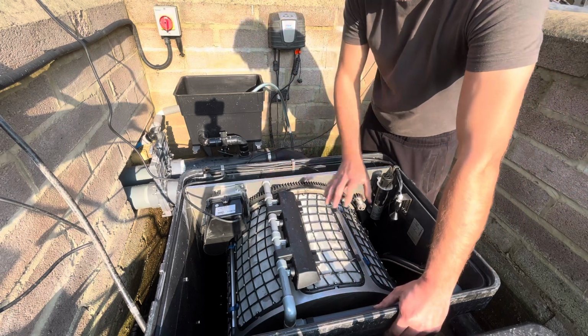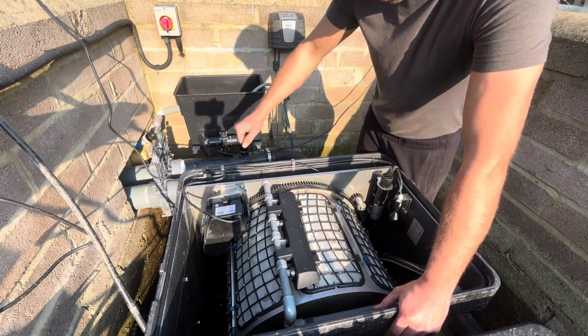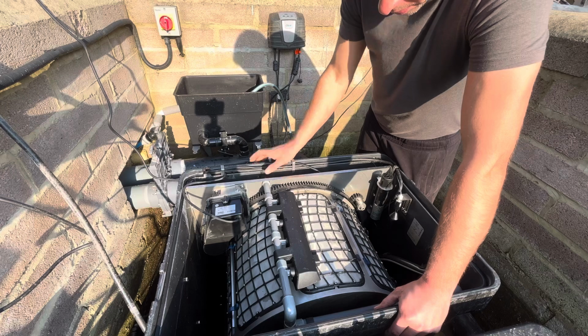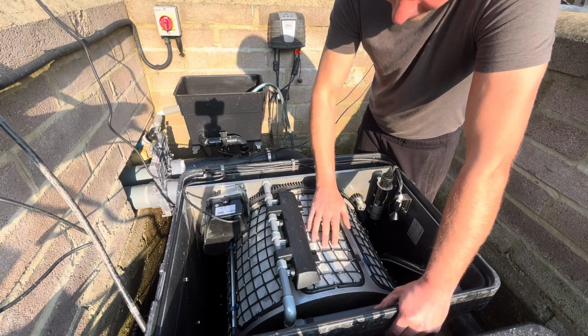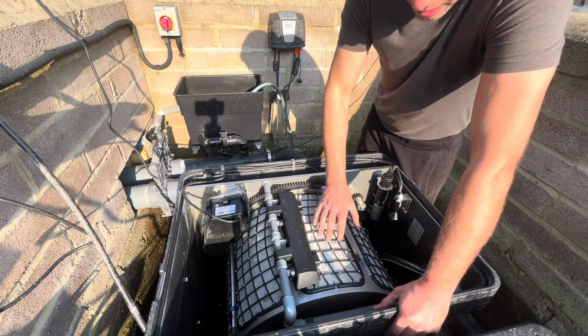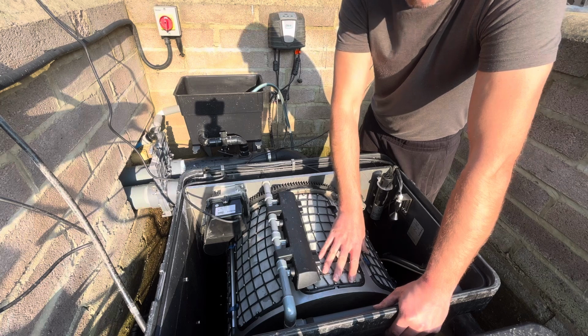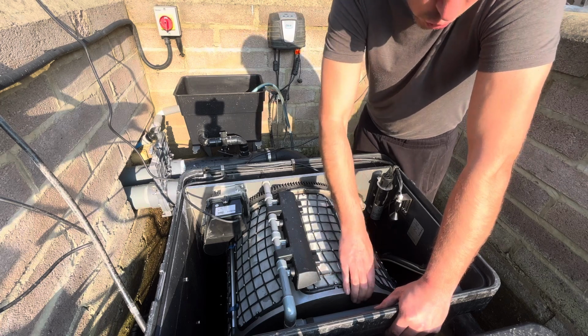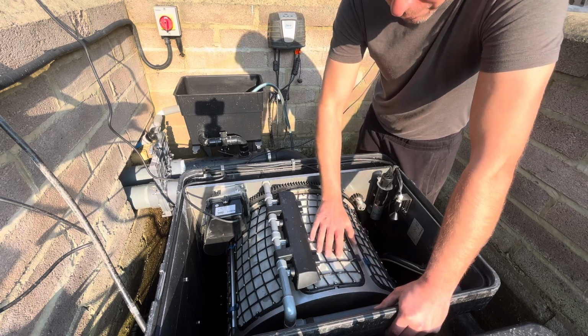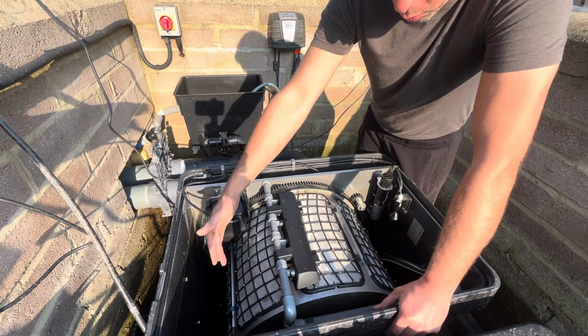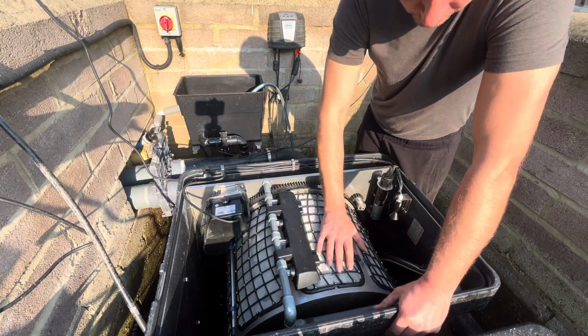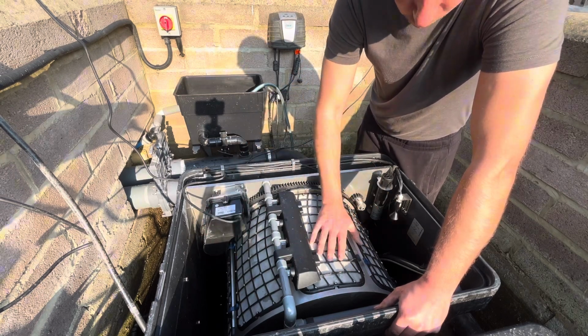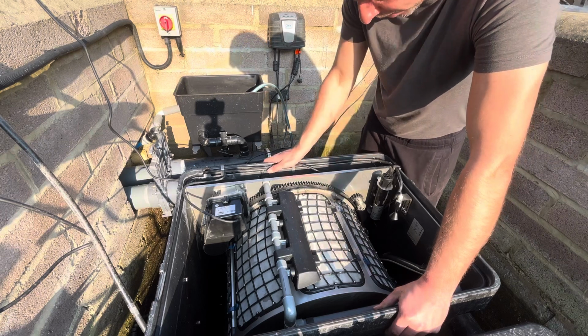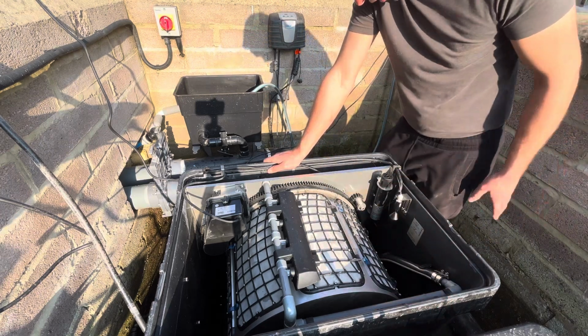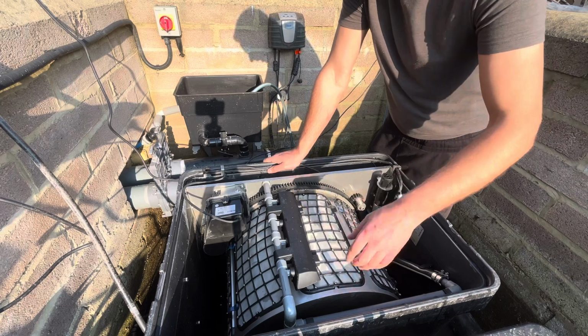It's very important once you pull this back together, never just open the gate valve straight open, because these will clog very fast as you're purging the drains through, and you can do damage to the screens, or even worse, damage to the drum. If it fills with water and there's not water around it, it becomes very heavy because it's completely full of water, so you can twist or bend the metal.